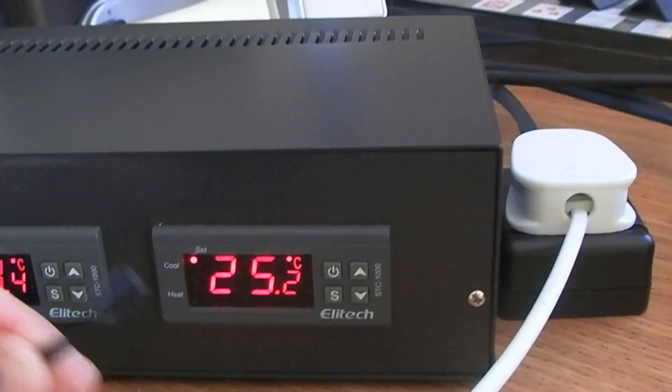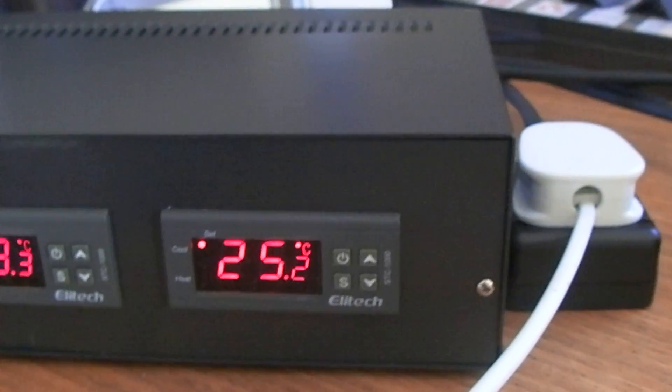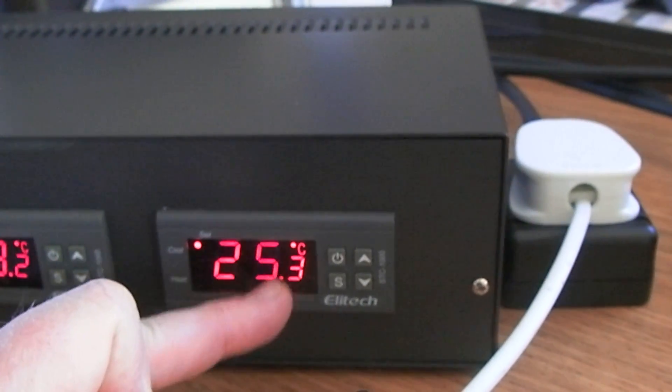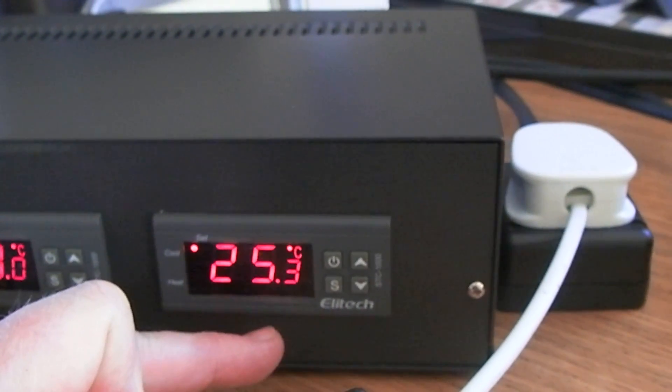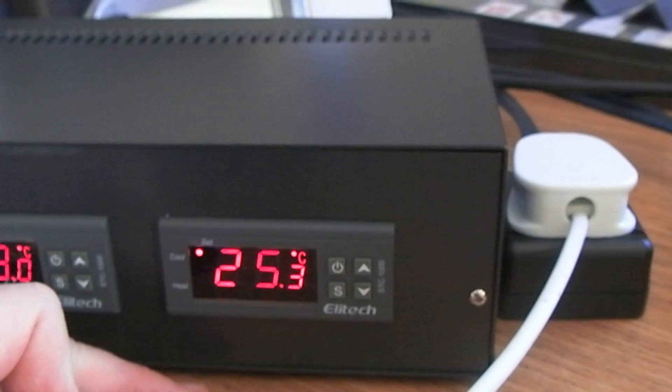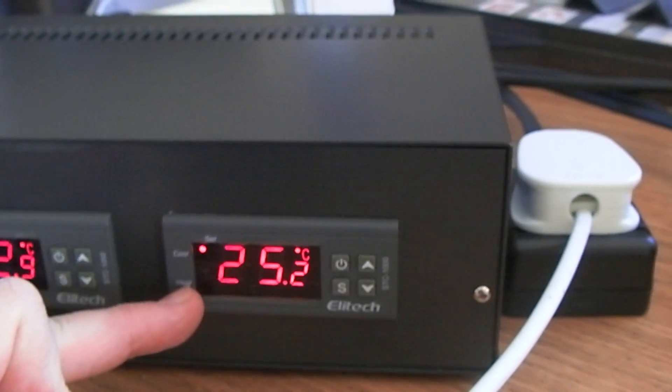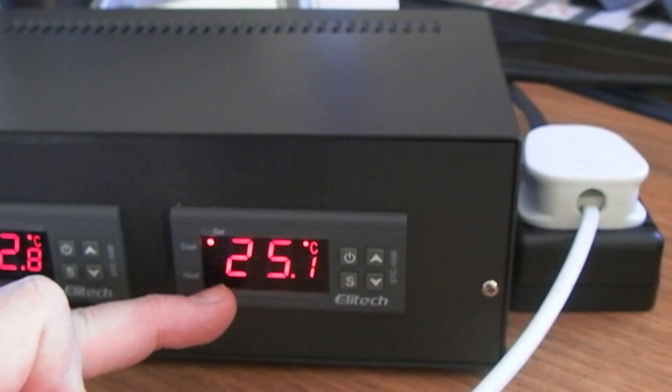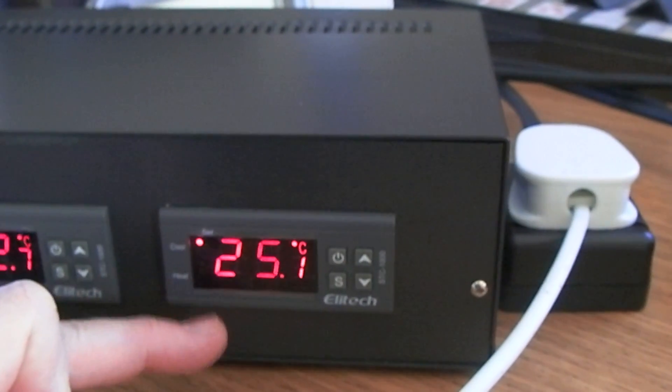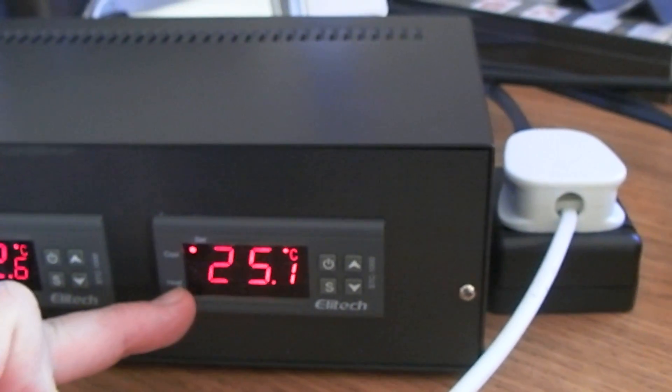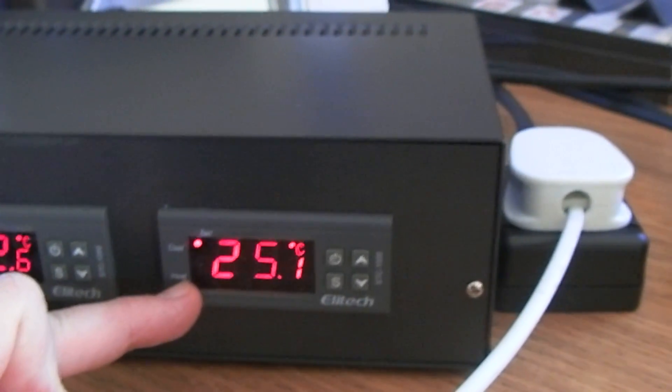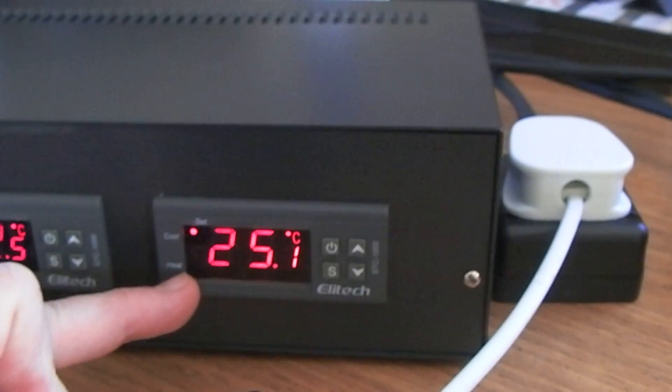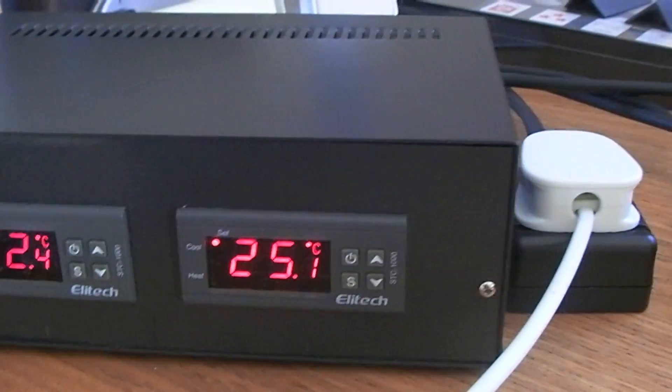There is a half degree offset. That's the lowest you can have. So when this drops back down in a minute to 24, it won't start heating instantly. It would allow it to drop to 23.5, and only then will it close the heat contact relay and repeat the process.